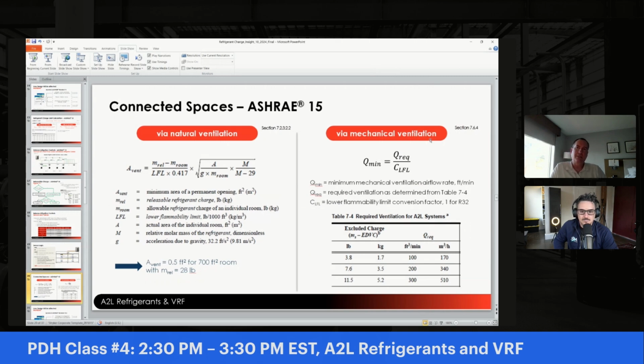Looking at connected spaces, with ASHRAE 15 2022, they added quite a bit of clarity around connected spaces with locations and calculations for sizing your natural ventilation openings. And it now offers a path to utilize mechanical ventilation with a separate equation here to calculate your ventilation airflow. Mechanical ventilation for this does not necessarily have to be outside air. It could be air from another connected space. And then the mechanical ventilation could either be continuous or just activated by the refrigerant sensor, either way.